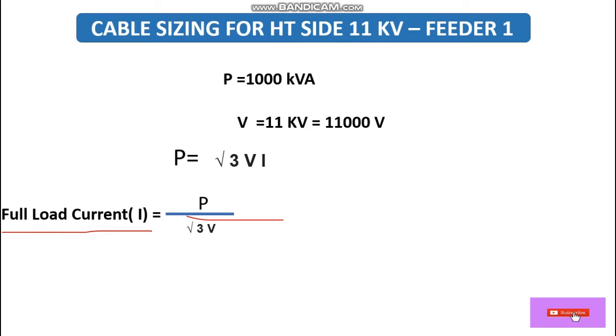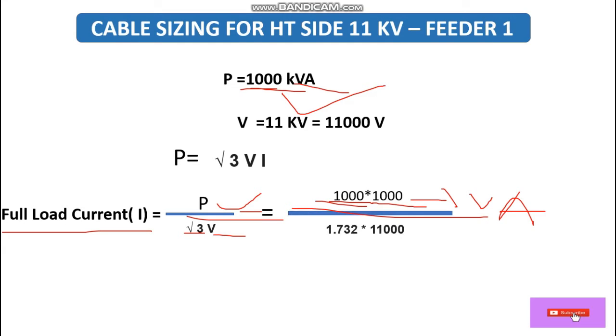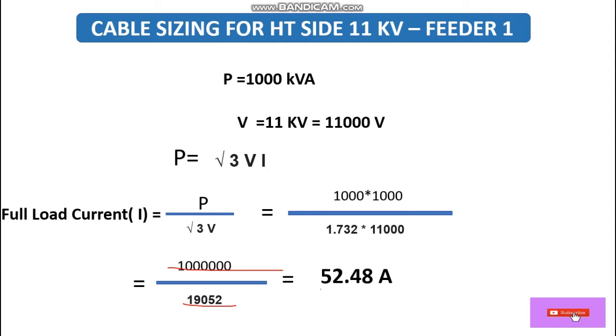Full load current = Apparent Power ÷ (√3 × Voltage). We convert 1000 kVA to VA: 1000 × 1000 = 1,000,000 VA. Substituting the values: √3 = 1.732, Voltage = 11,000 V. After calculation, the full load current comes to 52.48 amperes. This is the full load current on the HT side.